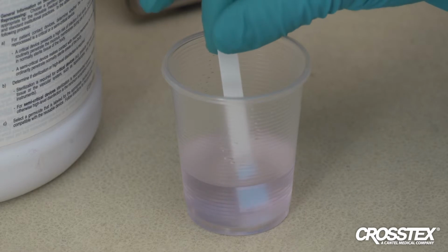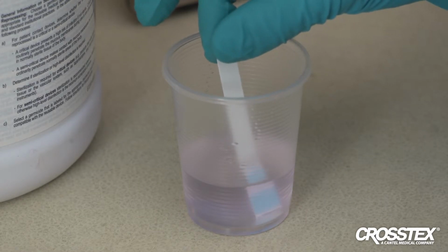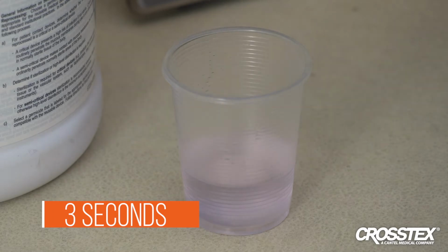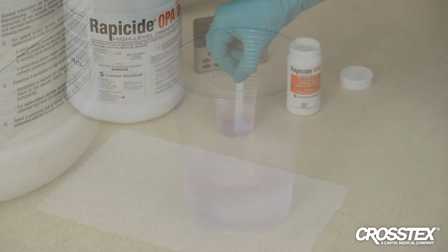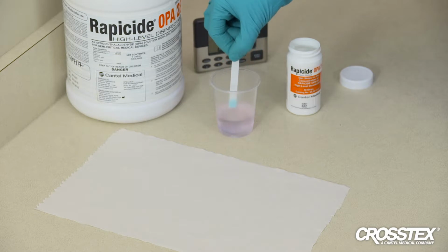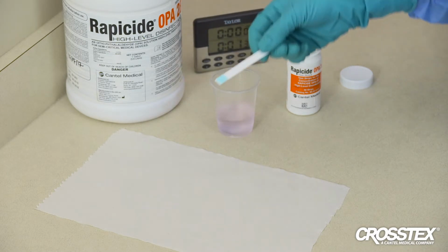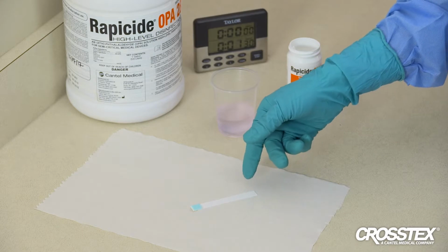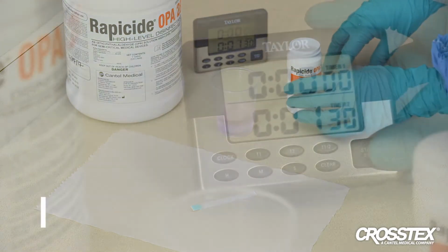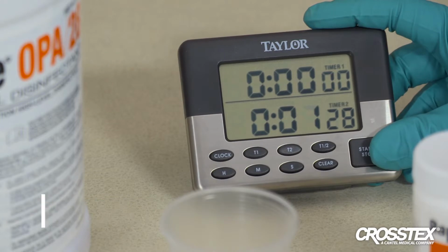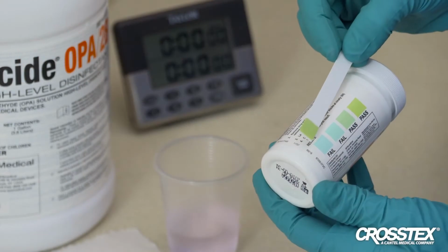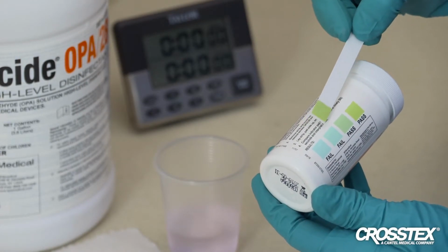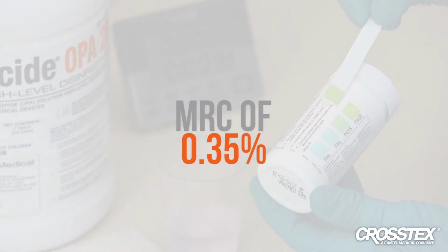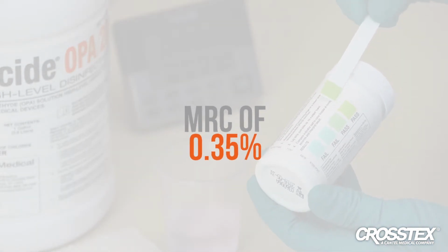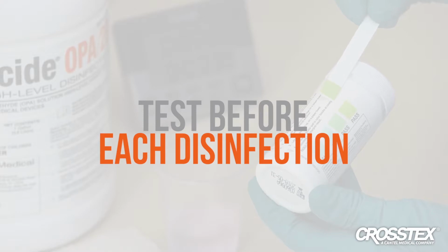Immerse the entire indicator pad on the test strip into the Rapicide OPA 28 solution for a full 3 seconds. Remove the strip and touch the long edge on the paper towel to remove any excess Rapicide OPA 28 HLD solution. Lay the strip pad side up on a paper towel and start a timer for 90 seconds. Compare the indicator pad to the color blocks on the test strip bottle at exactly 90 seconds and interpret the result. The color of the indicator pad will be green when the concentration of OPA is above the 0.35% MRC. Make sure to test the solution before each disinfection.